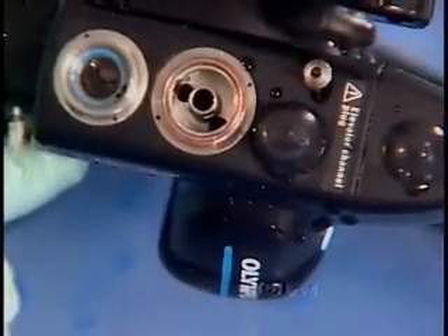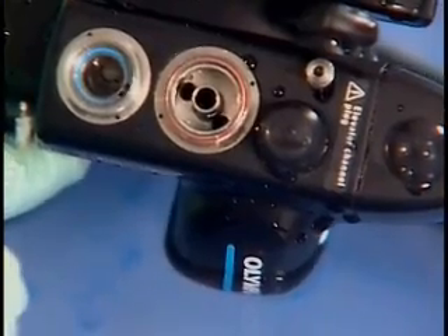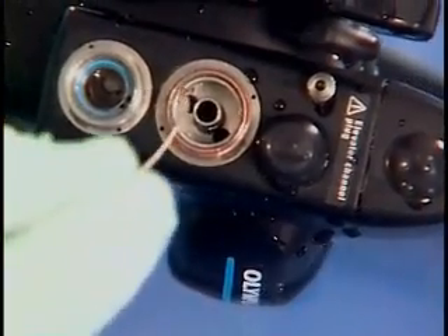To brush the balloon suction channel within the insertion tube, insert the balloon channel cleaning brush into the lower opening of the suction cylinder. Pass the brush through the insertion tube until it reaches the distal end of the channel. The brush will not exit the distal tip. Remove the brush from the channel and clean the bristles with your fingertips. Repeat until all debris is removed.